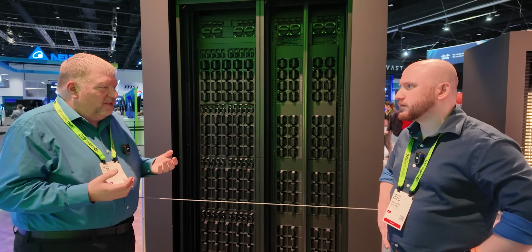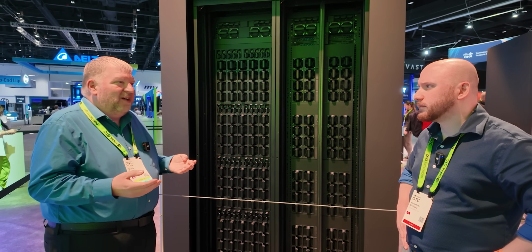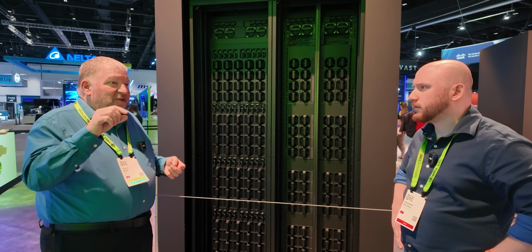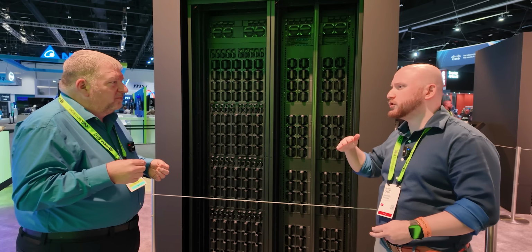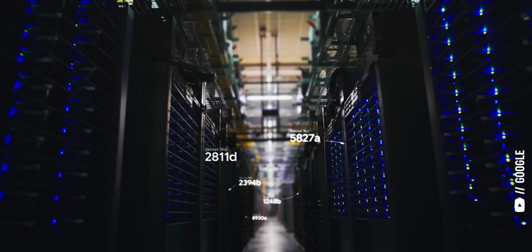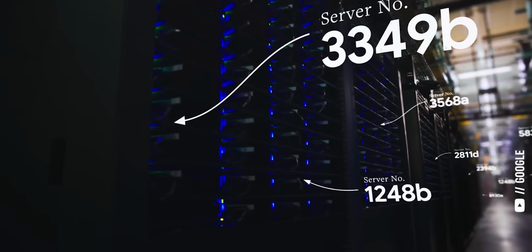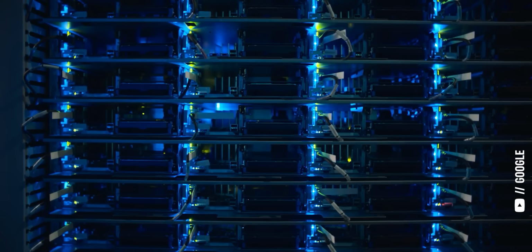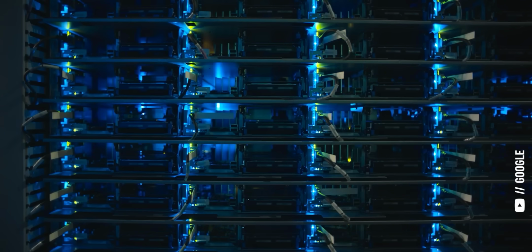And what's happened in the past, and this is a general computer industry issue, you always had to provision for peak power because you've got a steady running state, but at certain points in very small time scales, the computer needs a lot of power really quickly and then it goes back down. Which means you've provisioned for a lot more power than you're normally actually using, right? Correct. And most people today aren't building their own data centers. They're going to other data center providers. And when you go to those providers to get power for your cluster, your AI deployment, whatever you ask them for, they will give you, but you're charged for it. So if you ask for a megawatt of power because that's what you need for peak, you're paying for the megawatt whether you use it or not.